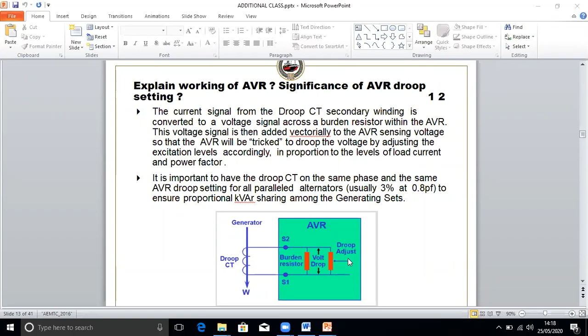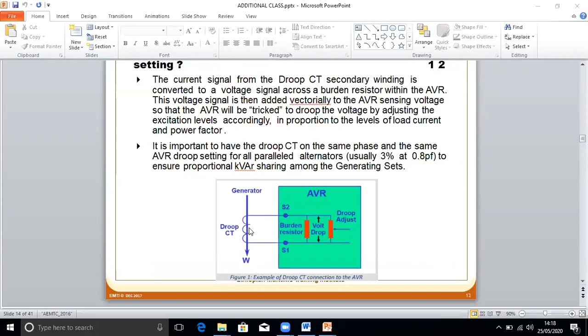Explain the working of AVR, significance of AVR droop setting. Droop CT is used to maintain reactive power of the generator. You have reactive power and real power. Real power is done by the governor, reactive power is done by the AVR. Droop CTs are ordinary current transformers. Which is the droop CT? This one. This is the droop CT.